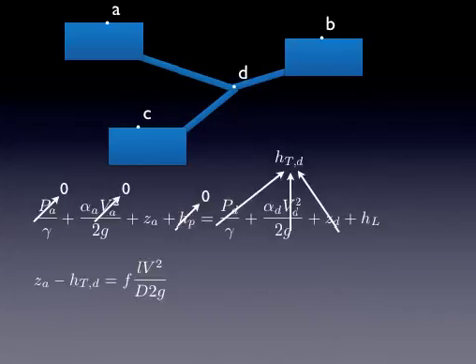So the equation reduces to this. We're going to use the Darcy-Weisbach equation for head loss, and that gives us this equation for velocity. So we can calculate the velocity in each of the pipes simply as a function of those changes in head and the friction factor and L and the diameter. Note you can also do this with the Hazen-Williams equation. You'd just have a different velocity equation that you would be using.